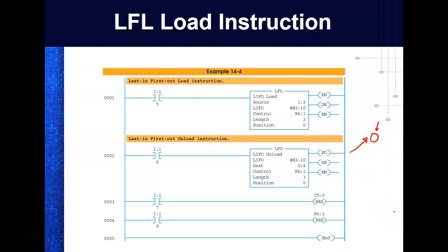So the big difference between us and the MicroLogix 1000s and the SLC 500 is that we can't change the original value of the index register. Now we can offset it into whatever data file we want to, right? Y'all understand that? But we just can't change what we originally start off with in the index register. So we'll always offset from 0.